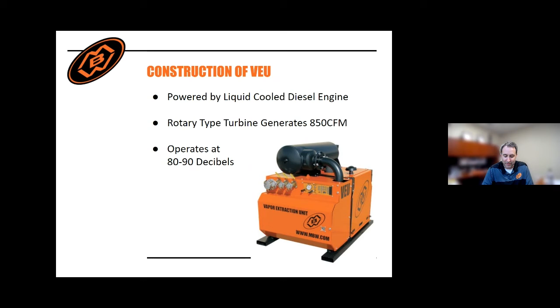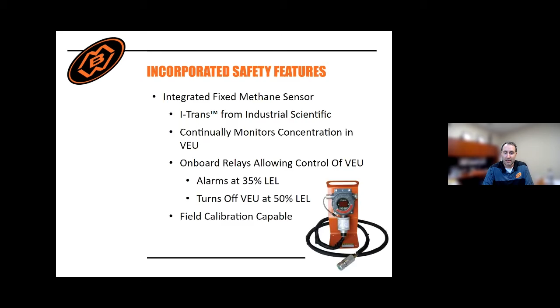The incorporated safety feature is that safety monitor. The way I like to describe it is it ensures that you never have 100% LEL moving through the entire system. It sets off an alarm. This is factory set at 35%. That allows the operator to make their adjustments. At 50% LEL, it shuts the machine down. So when someone asks me what happens when you have 100% LEL moving through the system, the answer is you don't, because the safety setup wouldn't allow it. And the other factor is that even if you did somehow manage to get a certain amount of gas into the system, the VEU is set up to pretty much just be a pass-through. There is no collecting type of tank, so you would have a very minimal amount internally at any time.